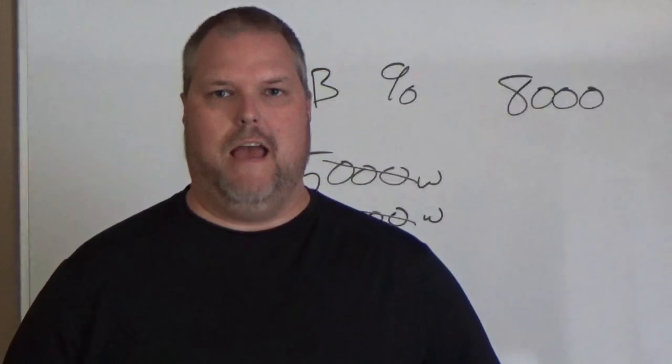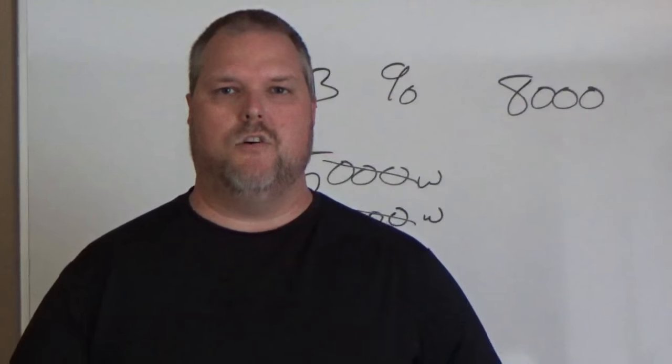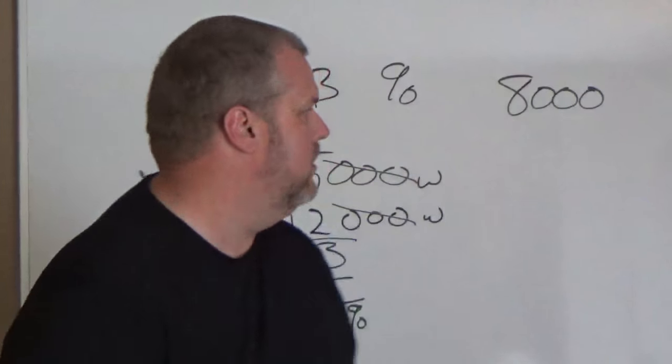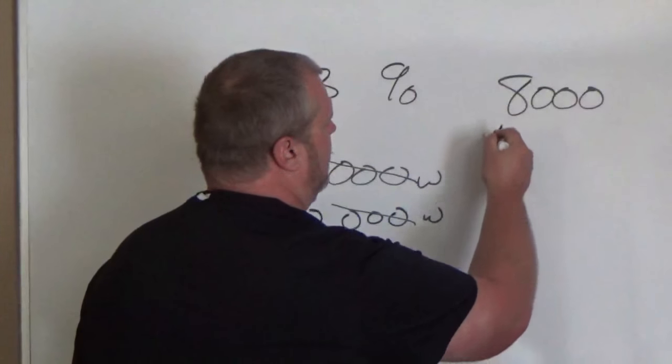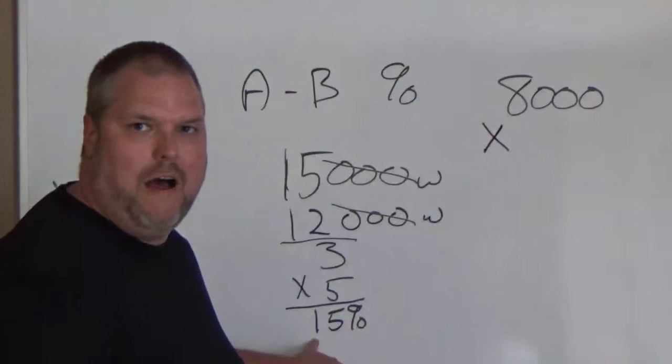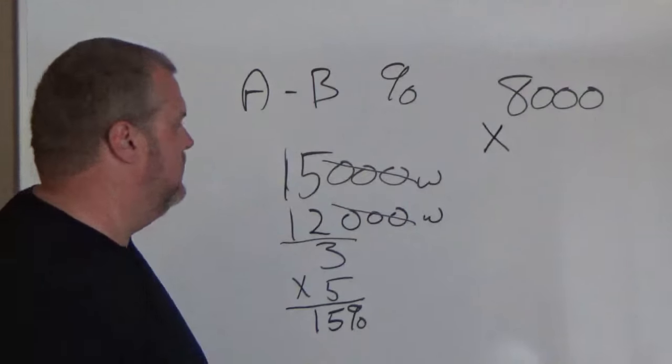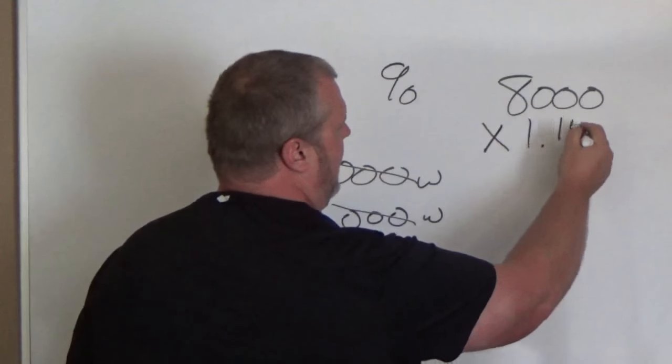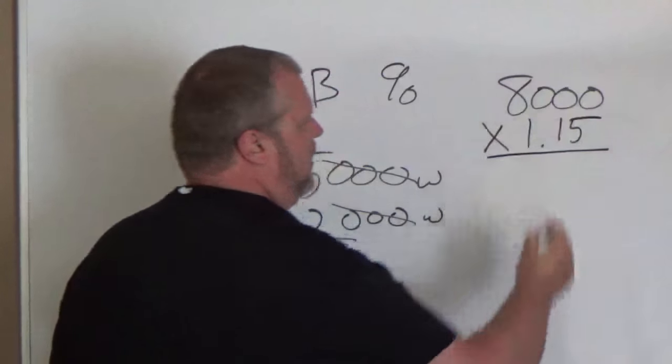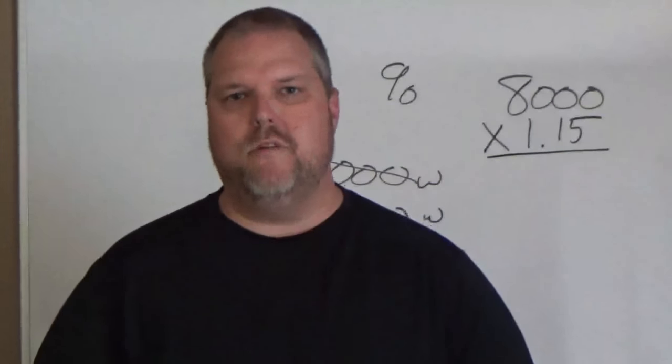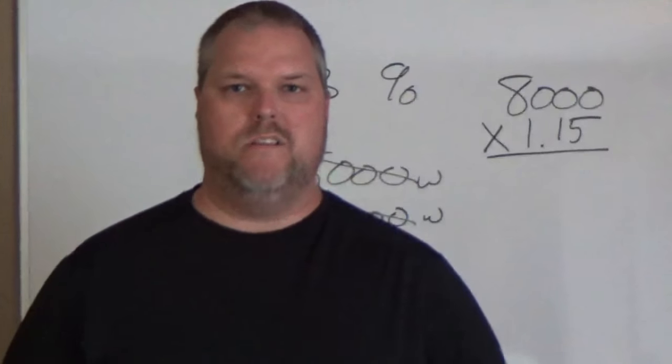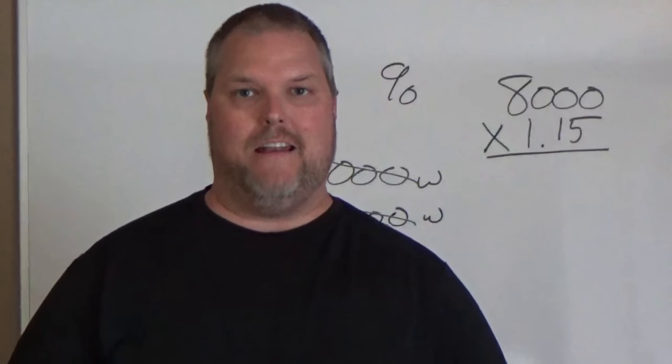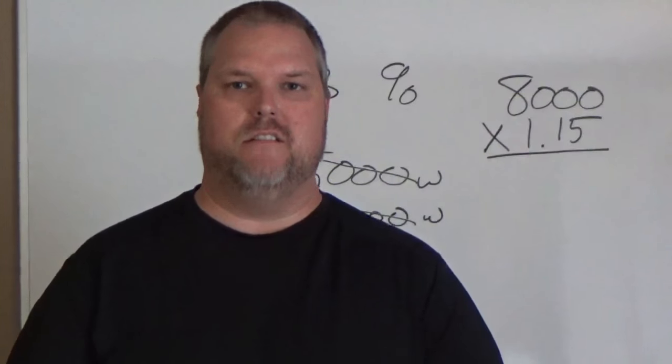Our demand starts at 8,000. How do I find out what my demand factor is for line 12? I know I have 15%. I'm going to multiply 1.15 by 8,000 because remember, we're dealing with one single range, so we're adding 15% to it.